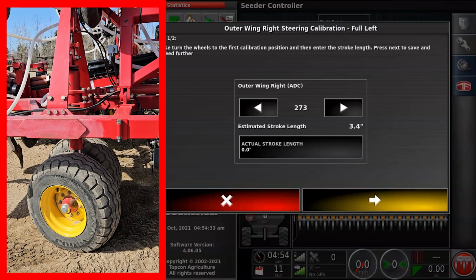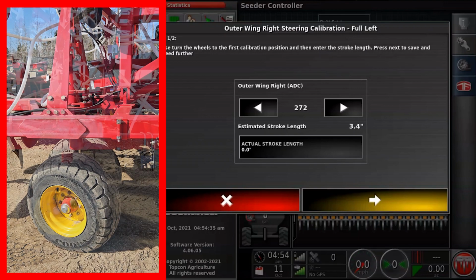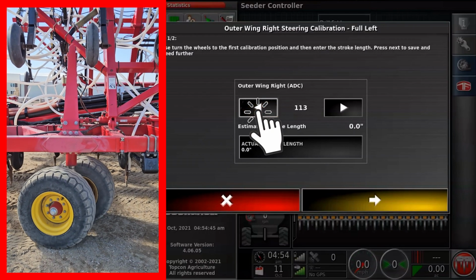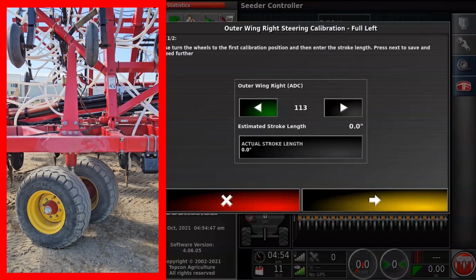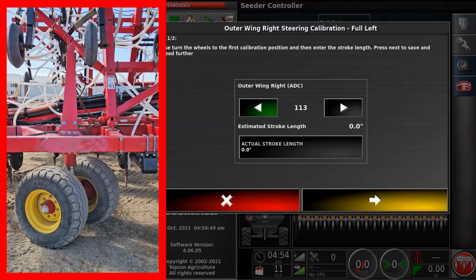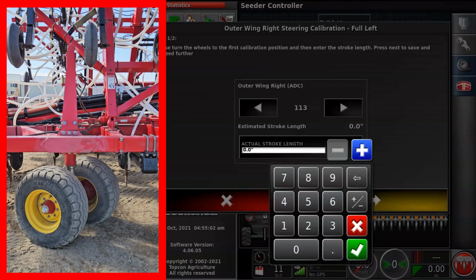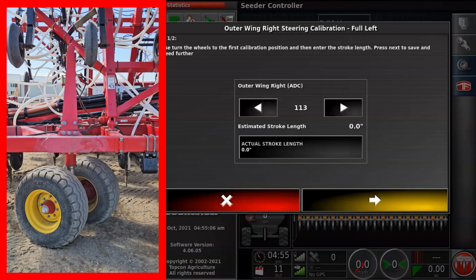We're going to fully retract that cylinder the same as before, clicking the button until you get to about 0, or you see your ADC level out. You've got to get out, check that cylinder, make sure it's fully retracted. Once confirmed, come back and hit your actual stroke length at 0, which it already is. Then we can hit that yellow arrow.